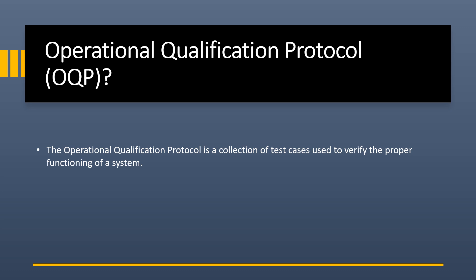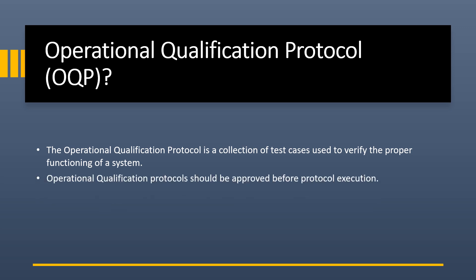The operational qualification protocol is a collection of test cases used to verify the proper functioning of a system. The OQ protocol should be approved by quality before protocol execution. Also, installation qualification must be executed and approved prior to starting operational qualification.